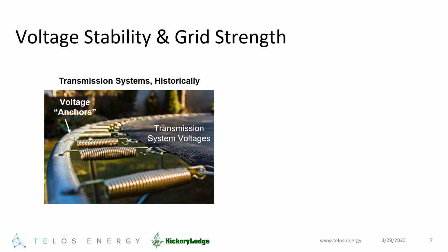In short, to think about the challenge here, consider a trampoline as an analogy to the transmission system voltages, with the canvas of the trampoline being at some level value where the voltages are nominal, supported by transmission lines, or springs in this case, and ultimately supported by voltage anchors, or the rail, which is conventionally those large synchronous machines. As you load up the system, as you apply weight to the trampoline, you get deflection in the trampoline, just as you apply load to the transmission system, you have deviations in voltages.